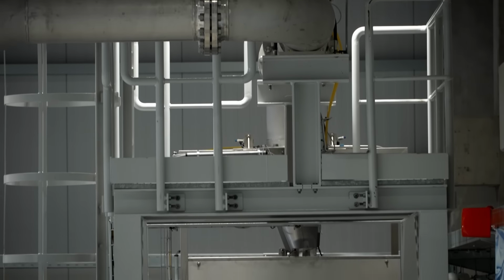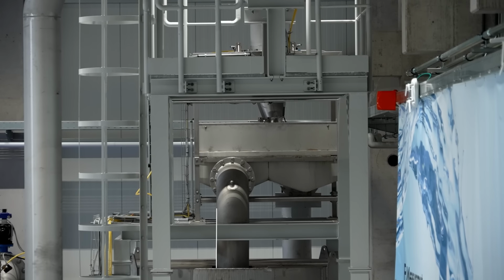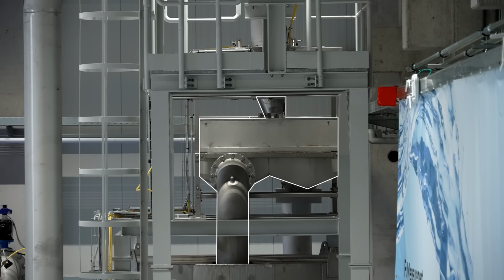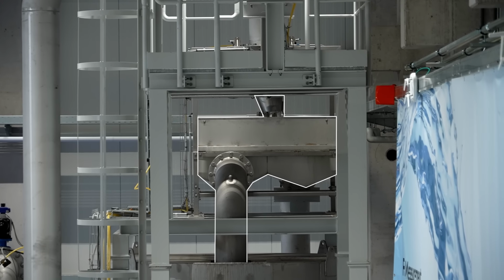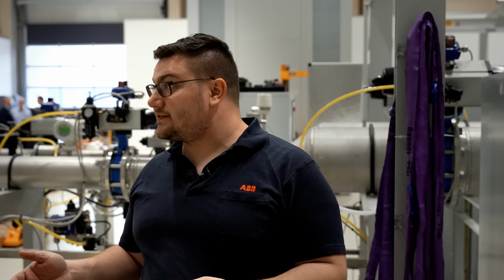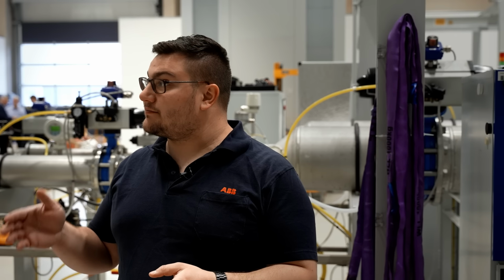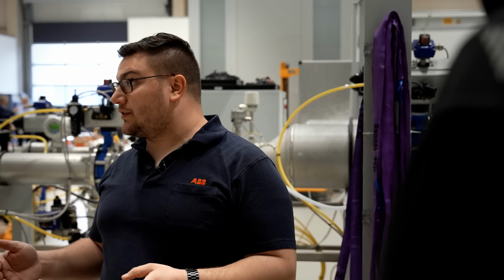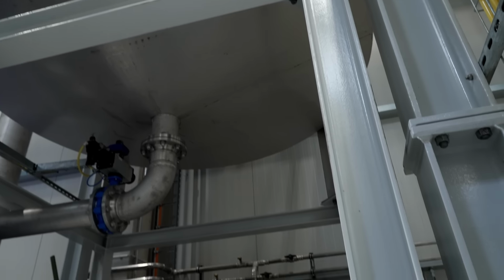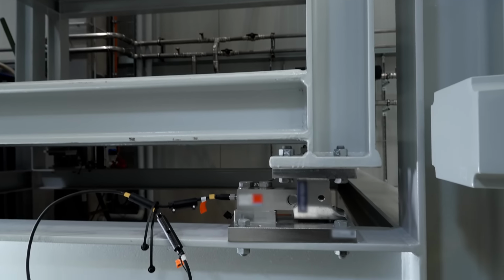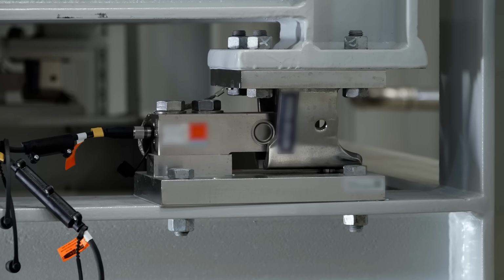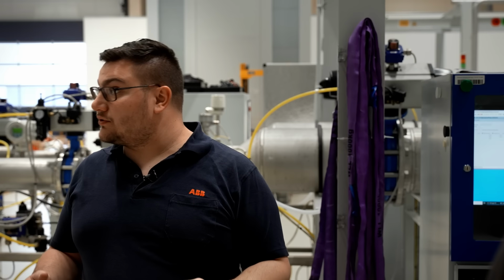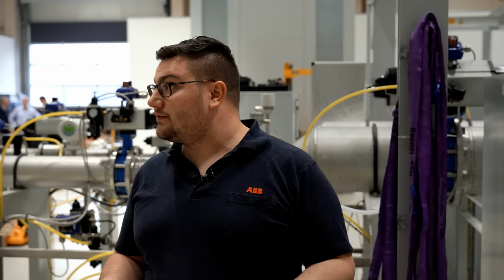When the water reaches the top of the tower, we actually get it to the diverter. The diverter directs flow between the main tank and the weigh scale tank. This switch of flow can happen in a few milliseconds, which helps us to have a precise starting point of the measurement and an ending point. For some of my colleagues, it is scary to get up there, but for me, it's just everyday business. This big gray weigh scale tank basically sits on top of a normal scale like you know from at home. So we have the scale, which has to hold up to 10 tons to make sure that we keep our feet dry when we have 7 tons per minute flowing in there.